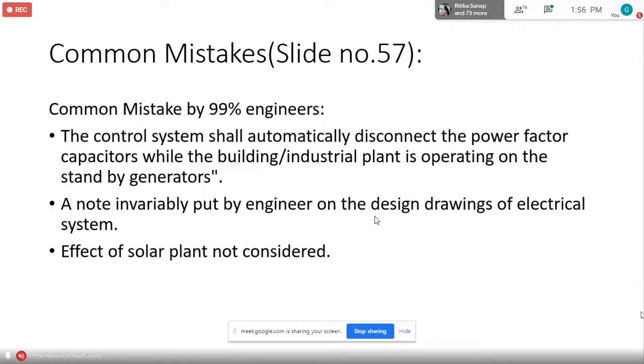They are not feeding only the capacitor bank. In that case, it is different. A generator cannot do more than 40% of its kVA capacity as a leading kVAR. So for example, a 1000 kVA generator will not be able to supply more than 400 kVAR leading power factor load. But it doesn't happen here. It is supplying the normal load. Effect of solar plant not considered.